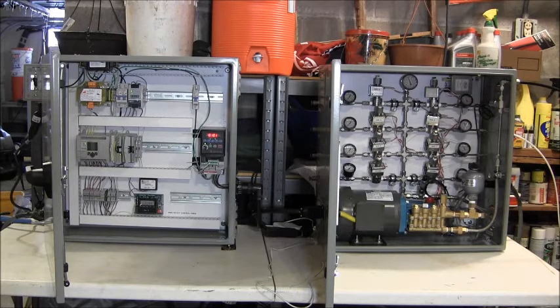These pressure transducers will shut down the machine also. If the pressure drops below 10 psi on the incoming water supply lines through this transducer, it will shut down the package. If the discharge pressure drops below 130 psi, which is where I've got it set right now, it will shut down the pump package. And again, if there is water in the assembly, it will shut down the pump package. That water sensor does have a 30-second time delay on it, so it's got to have water in the panel for at least 30 seconds, and then it will shut down the pump package.